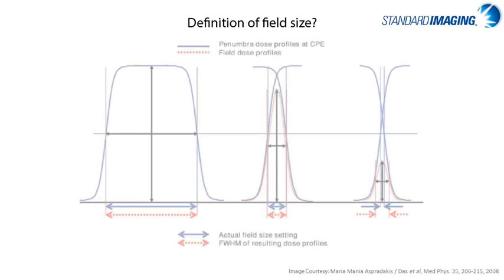If we extend that thought further, as the field size decreases, the traditional definition of field size using the full width at half max becomes irrelevant as the profiles are obscured by the collimators and the full width at half max actually gets artificially larger for very small field sizes, as you can see by the illustration on the far right.